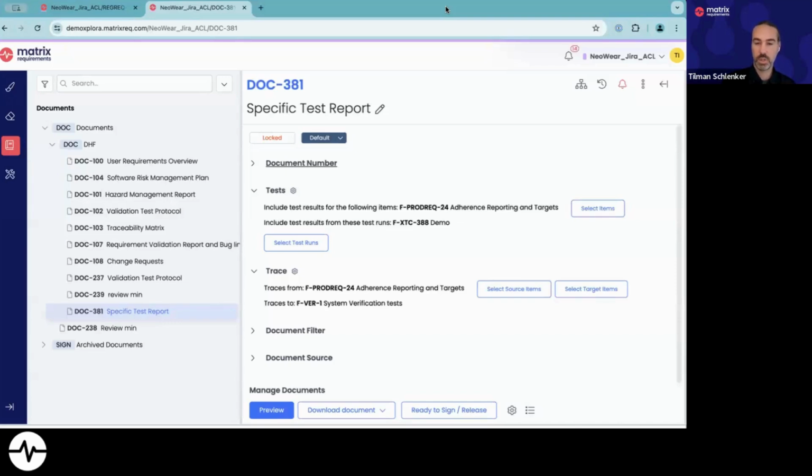You can either automatically populate this via a script based on the test results, or you can do it manually, and you need to attach at least the detailed test reports from your build system, potentially even the source code of your unit tests or the automation tests. But that's the important bit, because later on, if an auditor looks at the test results, he wants to have a complete view, and he doesn't want to ask you to go to the build machine and look at the result for that exact build. That's all that's interesting to him, because he doesn't care about all the builds that came before this release or after this release, at least not in this moment.